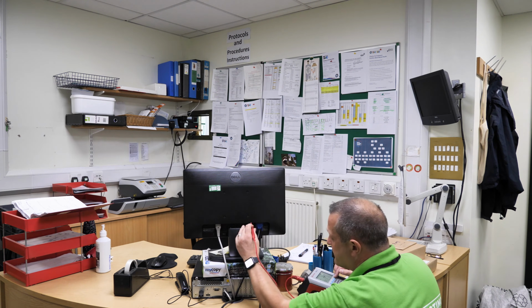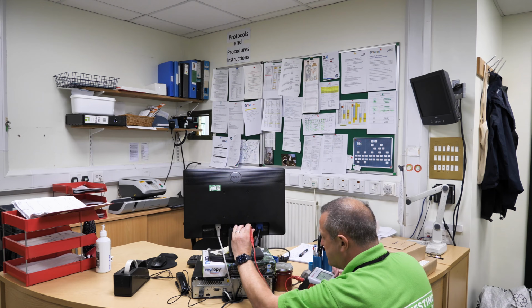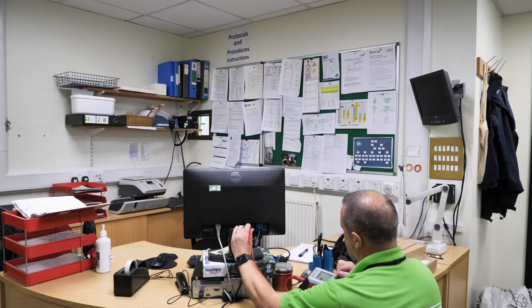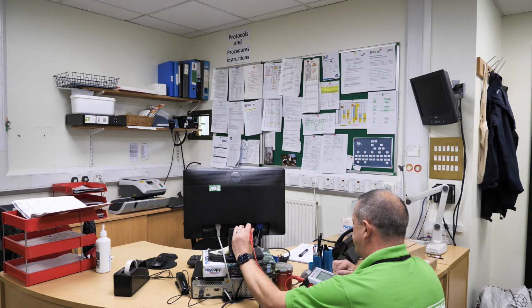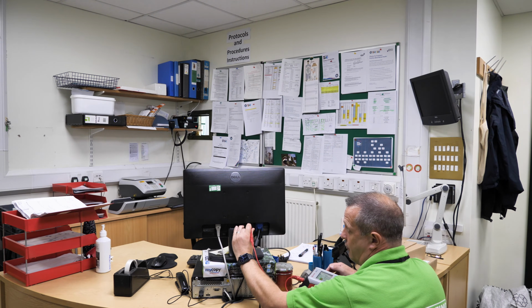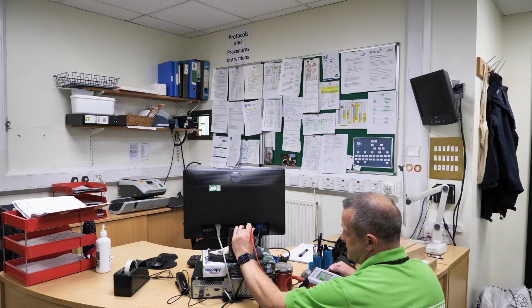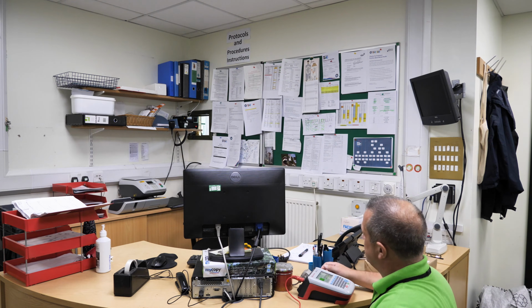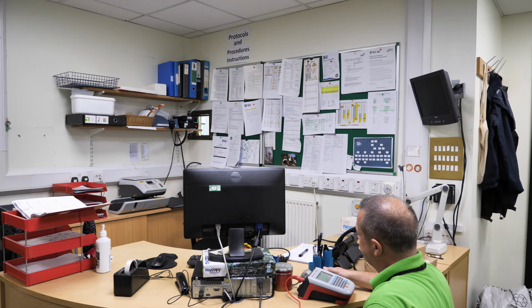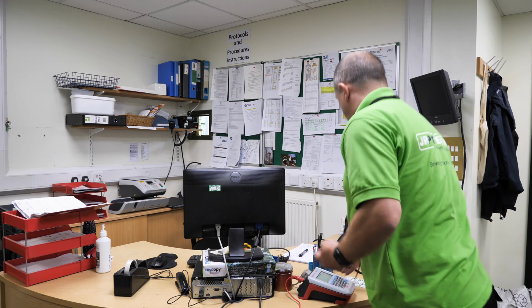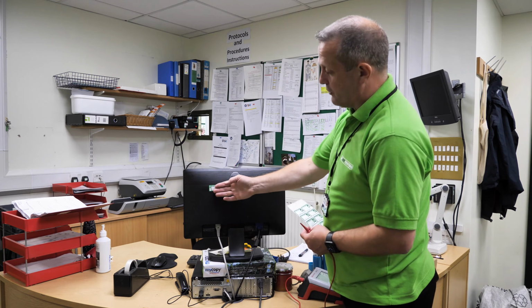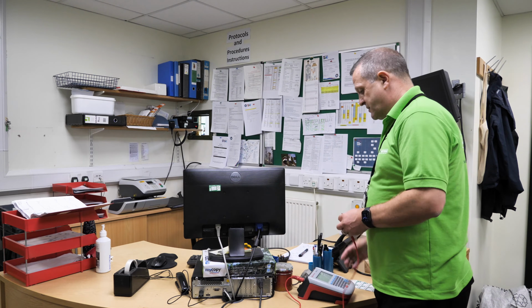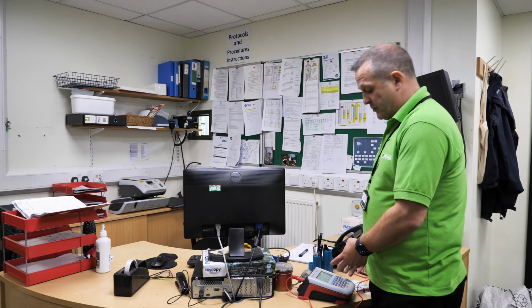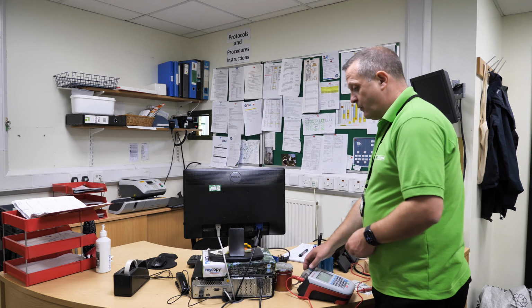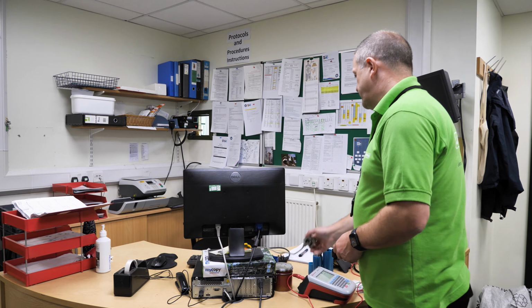So using the probe to find some exposed metal parts, we're then going to conduct a Class 1 test to test the earth continuity of the monitor. That's showing a very good result of 0.01, and then it'll continue through to the insulation test. That's all passed. So again, use a label. We would take off the old labels first, put a new label on to show that it's passed, mark up the results on the machine, and then we will move on to the computer base.